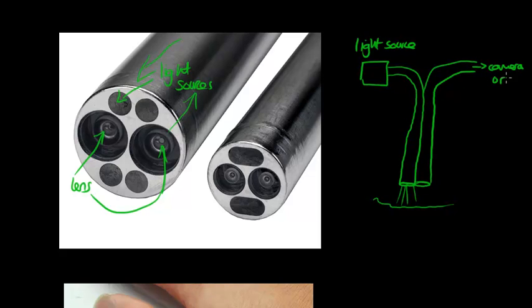To the camera or viewing lens. Okay, so the light is reflected into the lens. Inside each of these bundles there are typically about 10,000 optical fibers. And that's especially true for the image bundle because we need to form an image, so there will be 10,000 pixels making up that image.